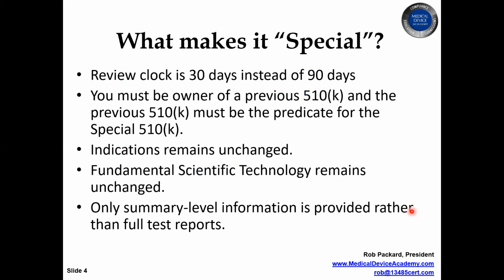Another requirement is you can't change your indications for use in any way. And the FDA in one place says indications, another place says intended use. They didn't make this 100% clear in the new guidance document that they released, but in general, the FDA has gotten much tougher on changes to indications. And essentially, the intended use, yes, that's broader, but the indications for use also really can't change.